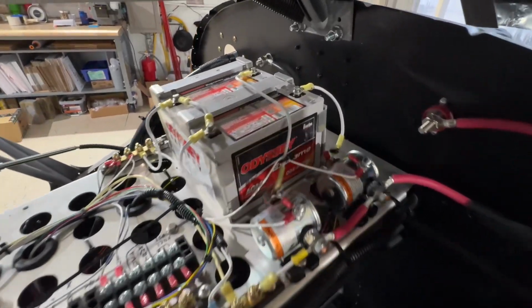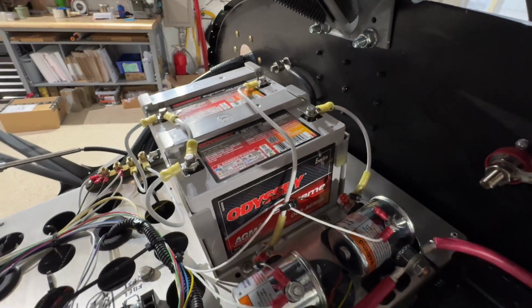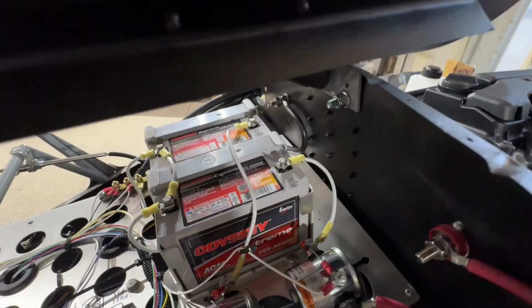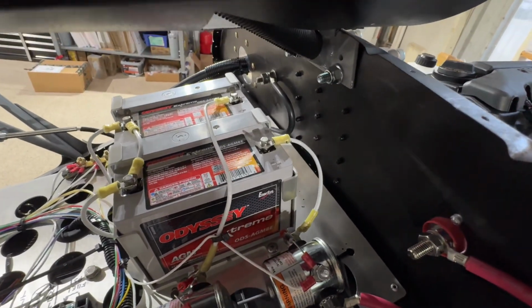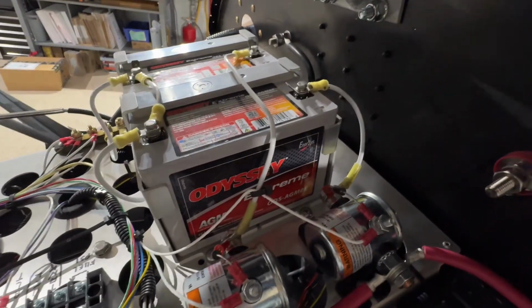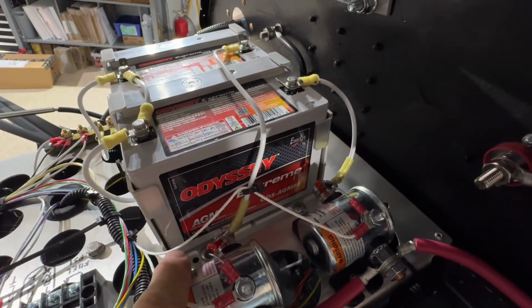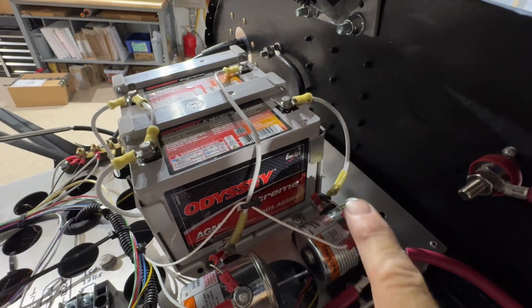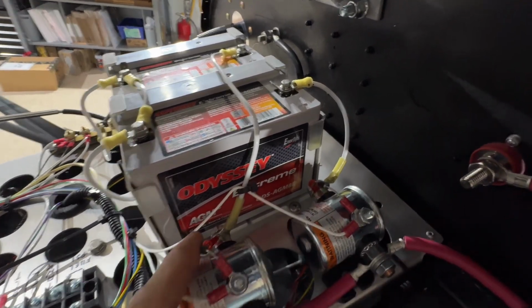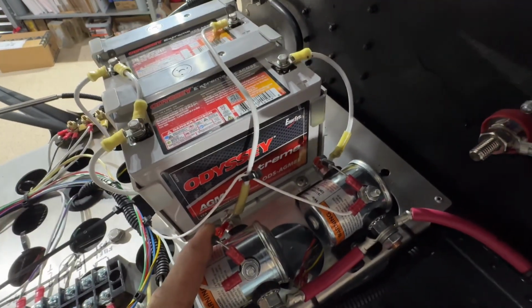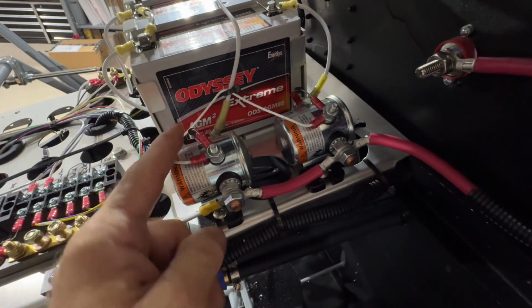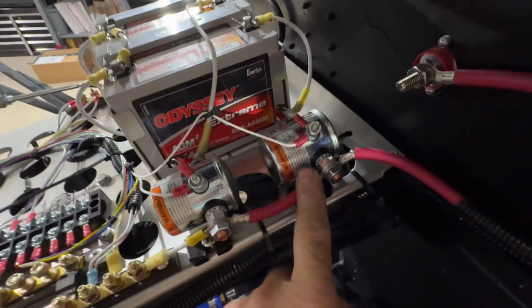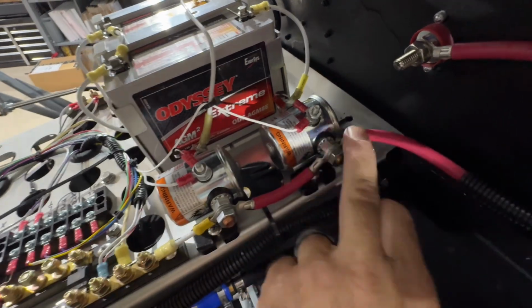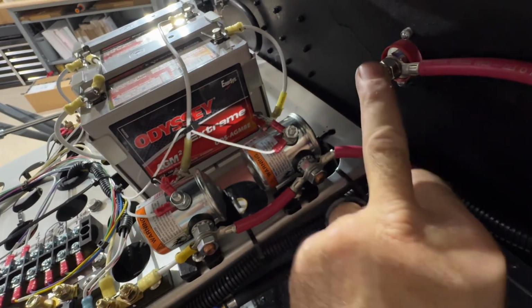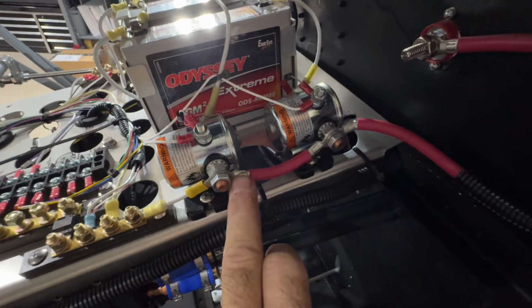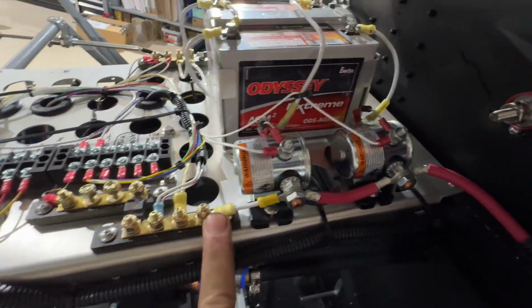Here we have the batteries mounted. Each battery is grounded separately, and each battery has a cable to its own individual contactor. Each contactor has a diode on it to prevent spikes, as shown in our wire diagram. At the output of the contactor, they're tied together, so when both are closed we can feed power to the starter motor, and we can also feed power to the rest of the airplane.